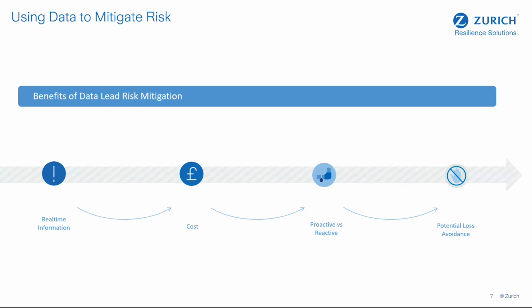The last one is potential loss avoidance, and I'll give you an example here - one that we in Zurich had ourselves. It was in a comms room, and we had an air handling unit that was not working properly. There was a blockage, and basically a buildup of water. Humidity levels went high. This was picked up on the actual building data, and we were able to rectify that and prevent potential loss.